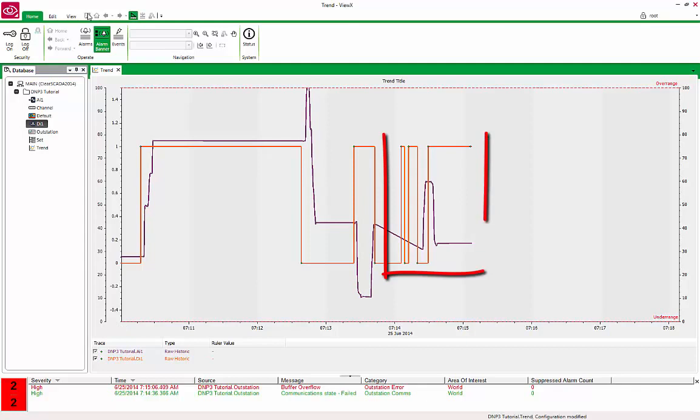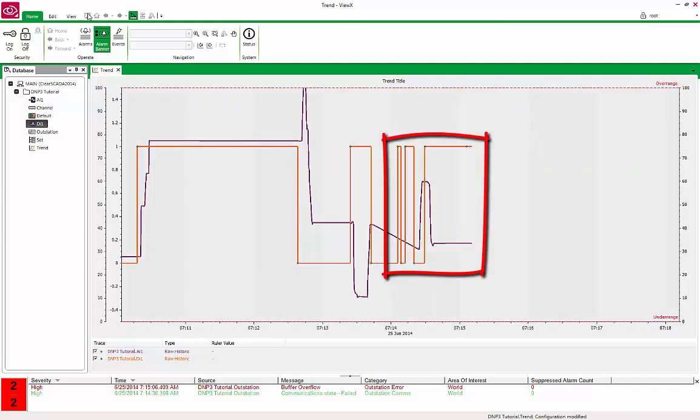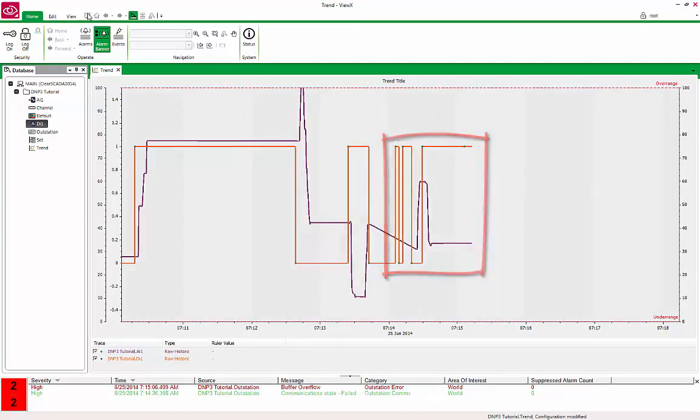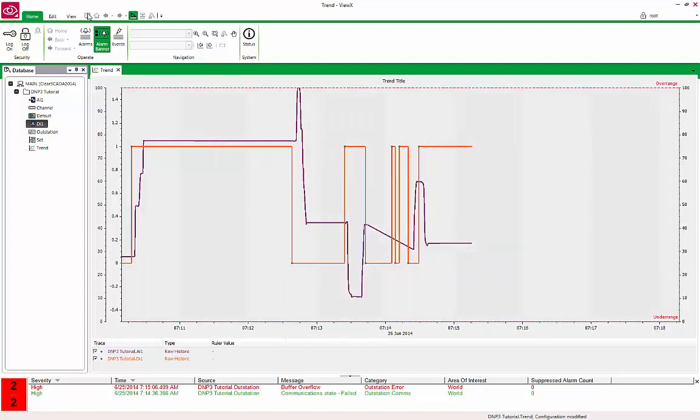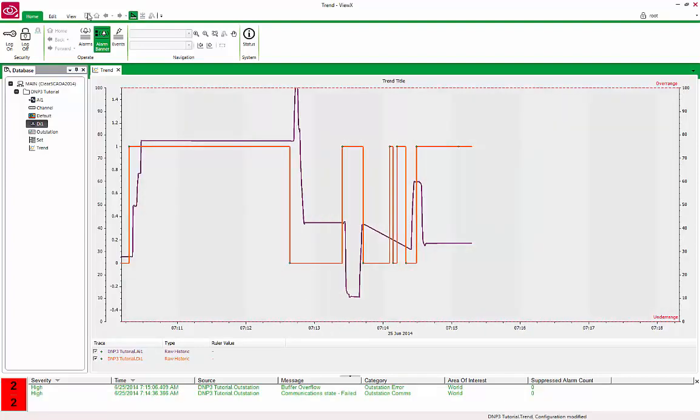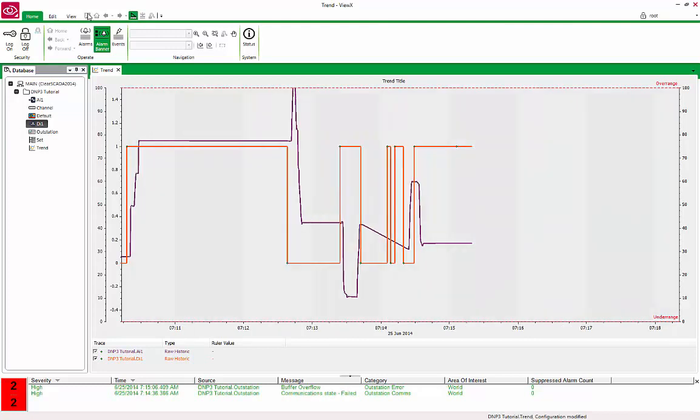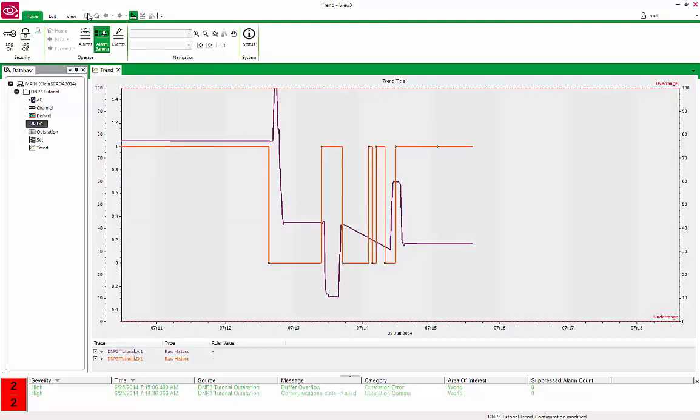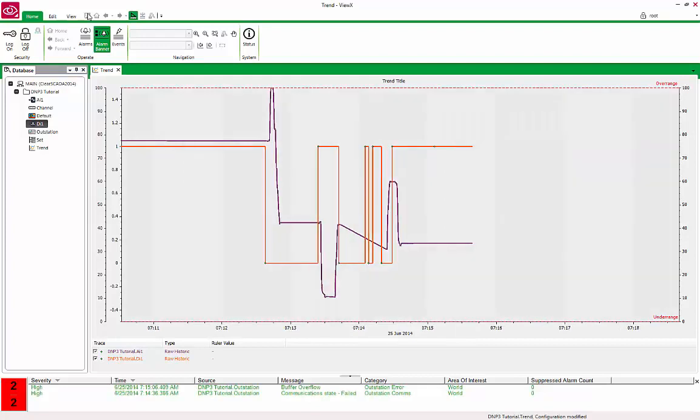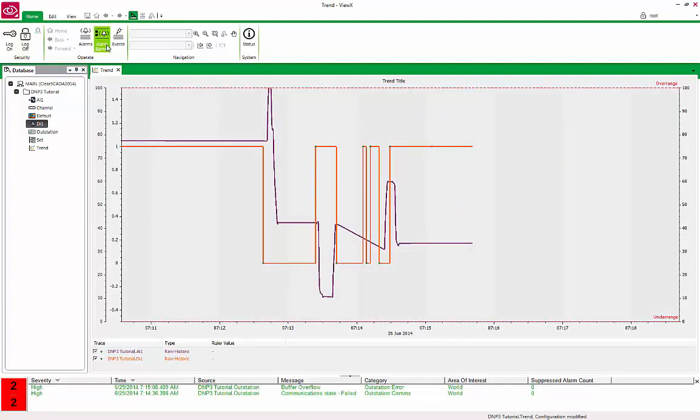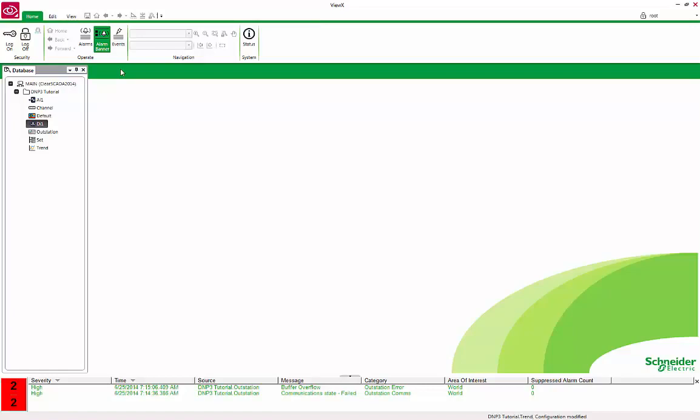As you can see, the data has now appeared on the Trend because it was being stored in the DNP device. Everything that occurred during the communication loss period is transferred to ClearSCADA when the communications was reestablished. The history is maintained by default, and the user now also has a record of the communications failure in the event journal for future analysis. This is one of the key benefits of DNP3 in that a communications failure does not mean a loss of critical process data, billing information, or data mandated for regulatory compliance. The DNP device keeps a record of changes happening.